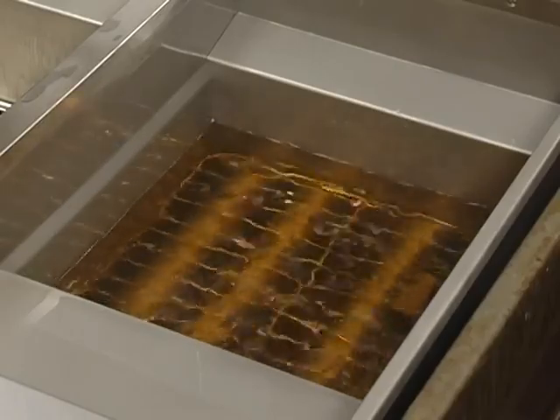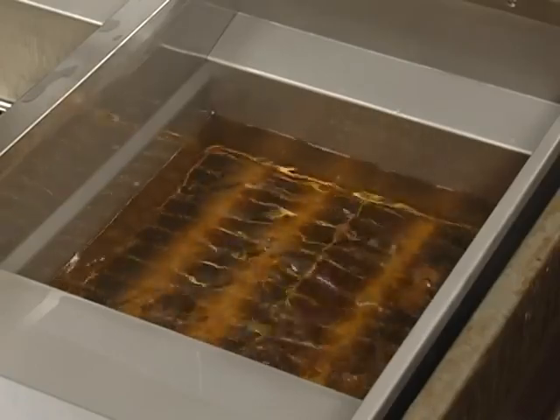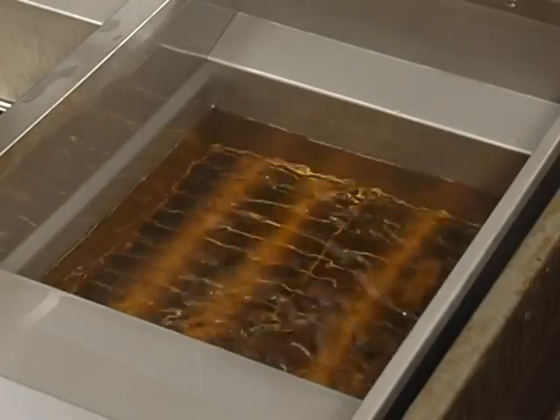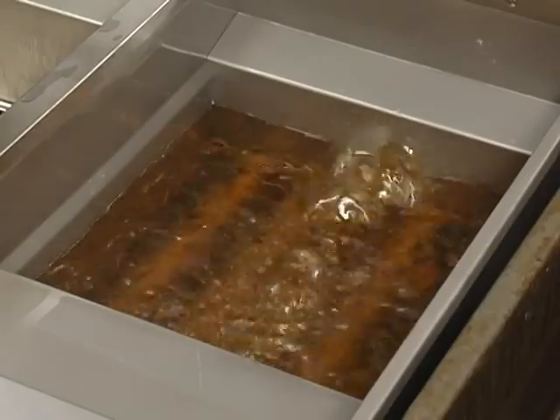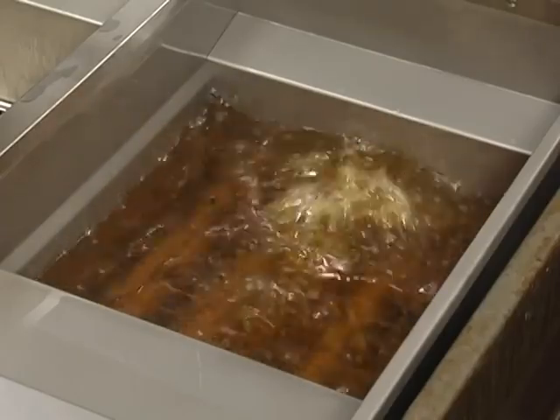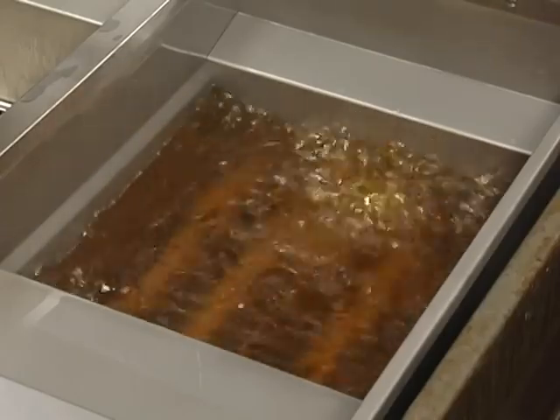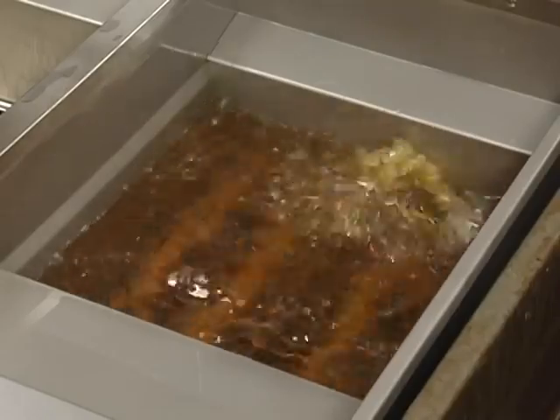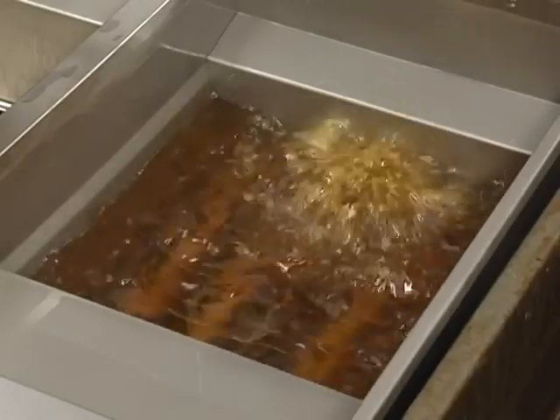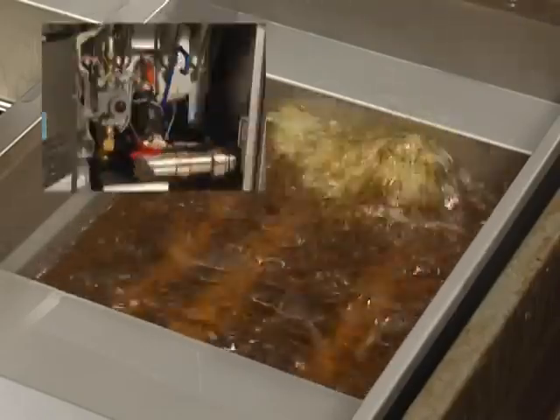Once all the oil is pumped back into the tank, you'll start to see bubbles emerging from the oil. Allow the pump to run for an additional 10 to 15 seconds to return any leftover oil from the filter pan or the filter return lines. After 10 to 15 seconds of bubbles, close the valve and stop the pump by pushing the red return valve handle in.